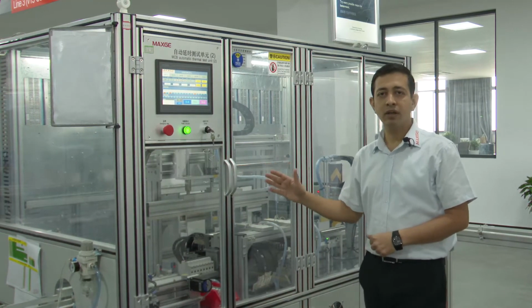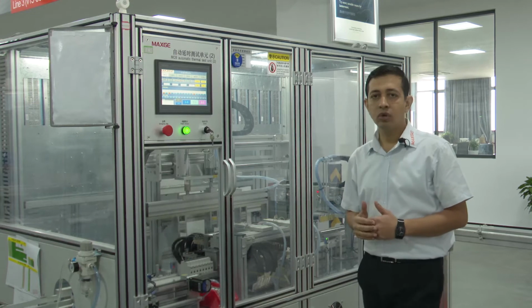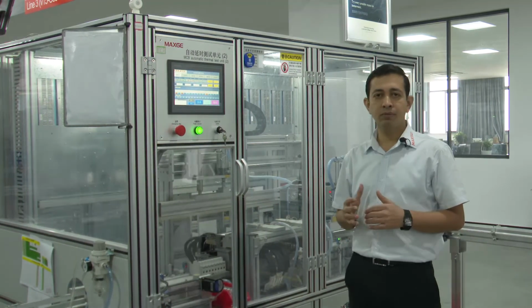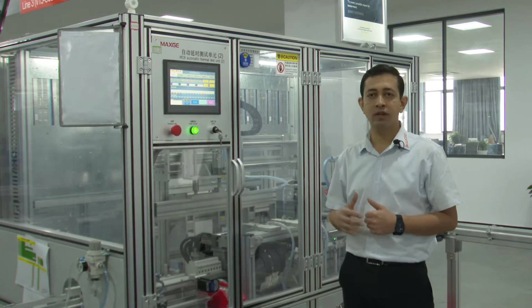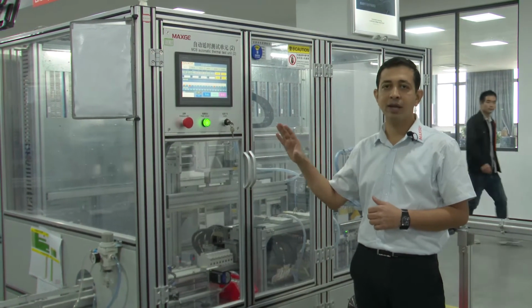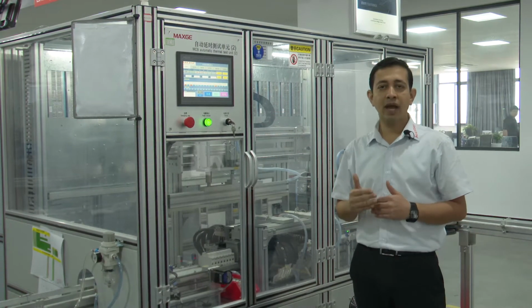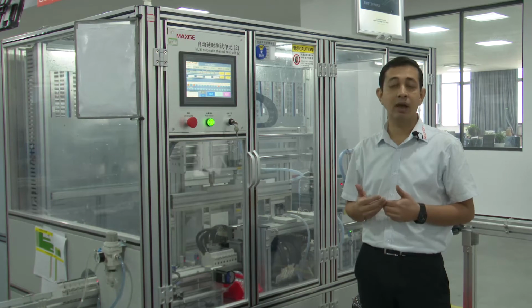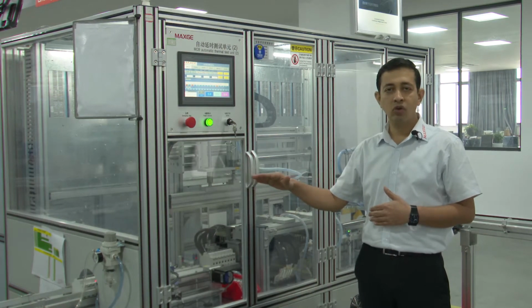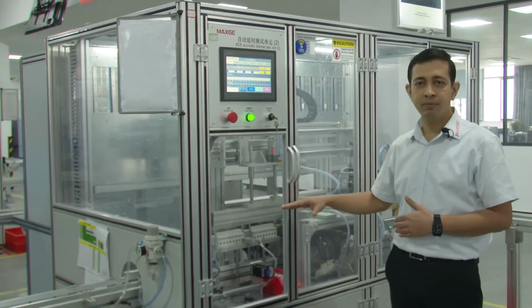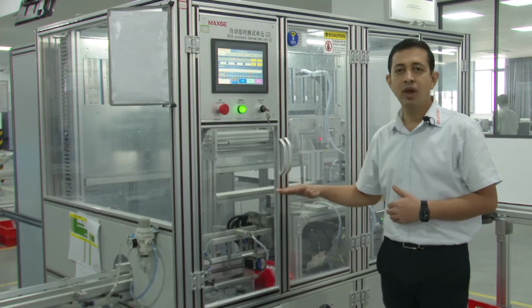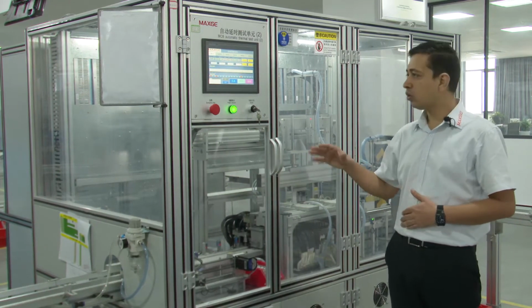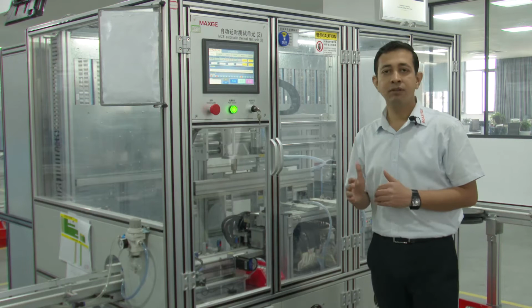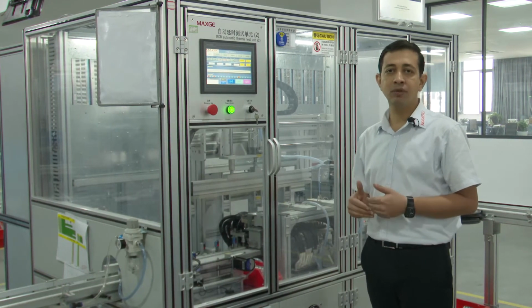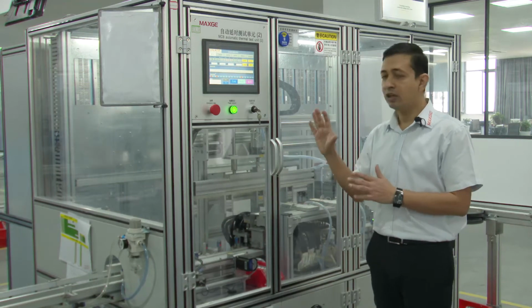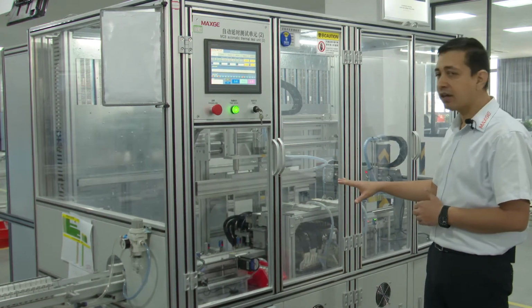What is this magnetic testing for? This is basically to ensure that the MCB trips, because an MCB has two protections: one is overload and the other is short circuit. The short circuit protection is taken care of by the magnetic testing in our factory, because we cannot pass the actual short circuit current, otherwise the MCB will get damaged. So we pass a certain amount of current. This is a C characteristic MCB, wherein 5 to 10 In current has to be passed. At 5 In the MCB should not trip. At 10 In the MCB should trip within 100 milliseconds. This is what the standard says. So this machine automatically does the magnetic testing.